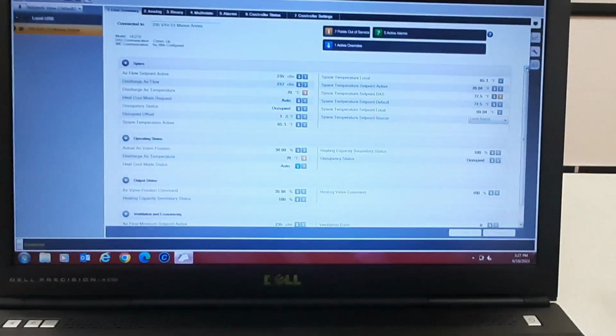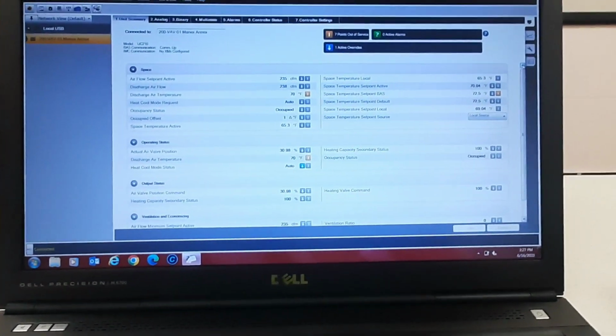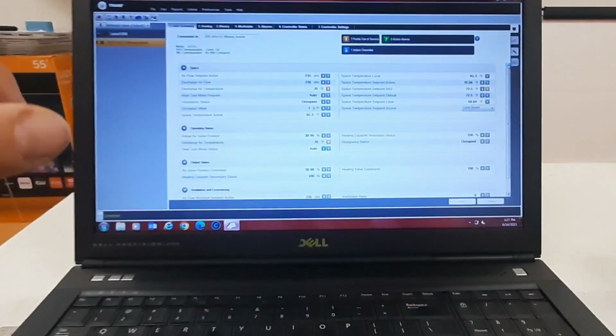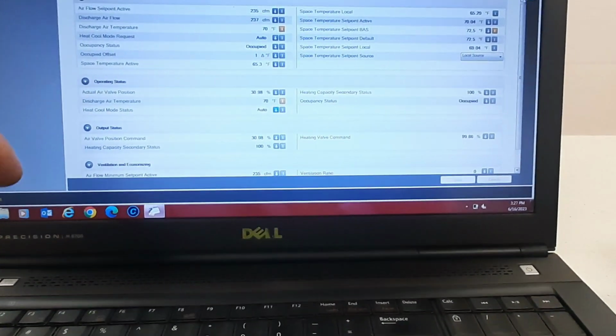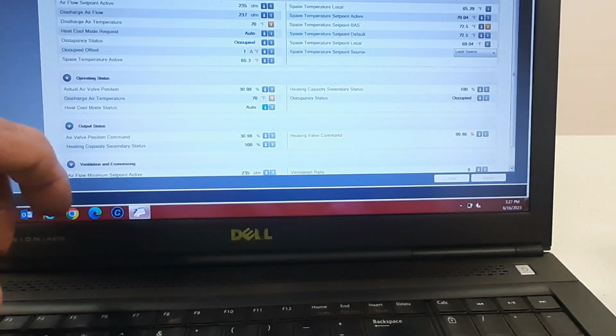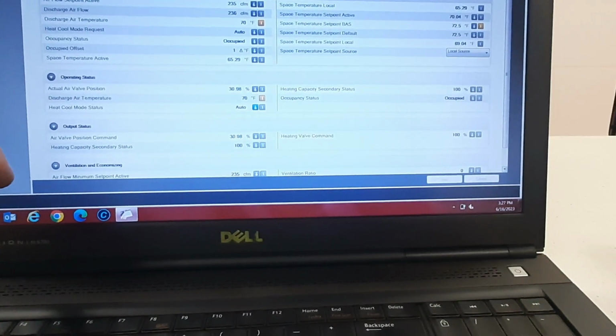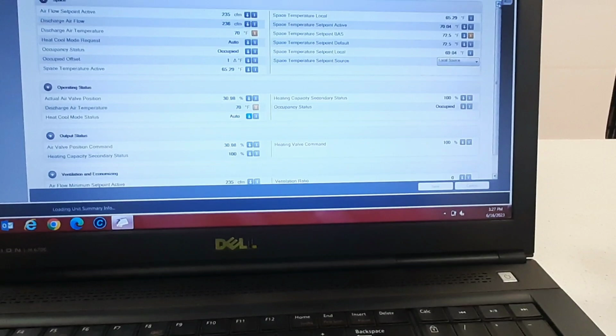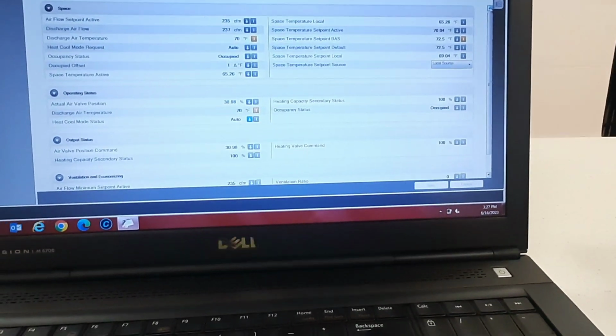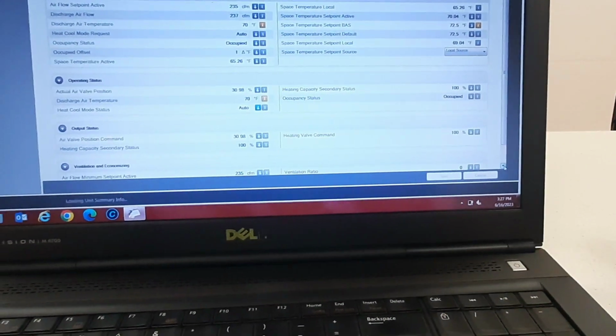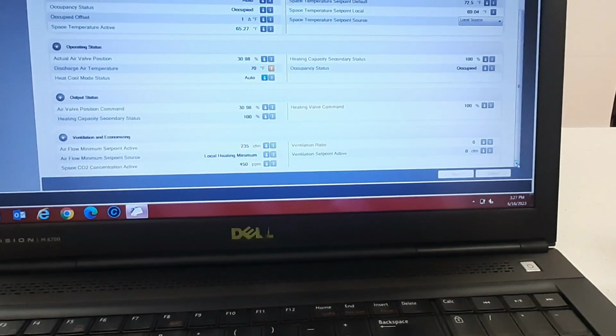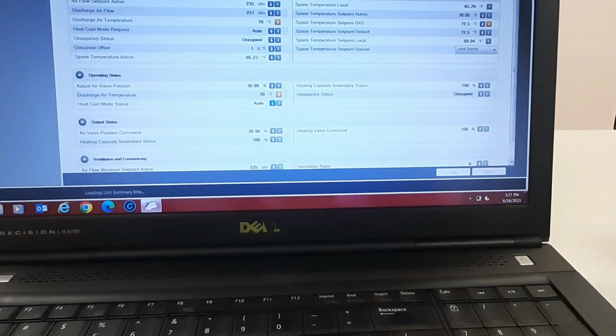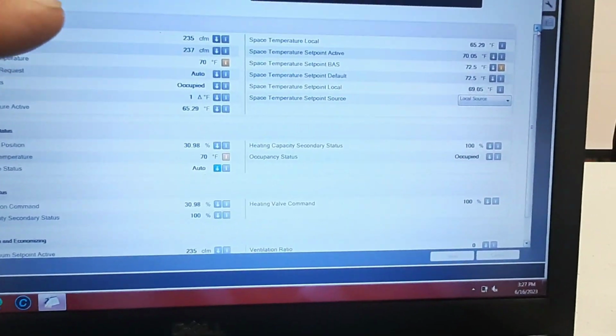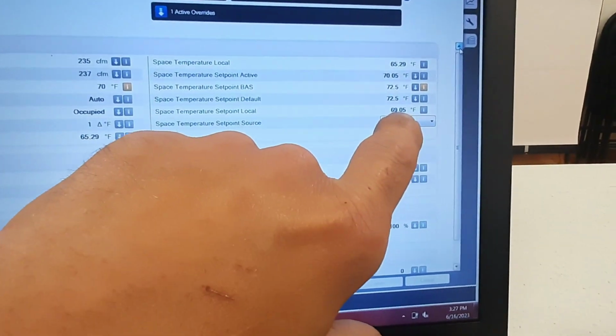So this thing, apparently where it was showing test, I don't know if it got stuck in that calibration mode or what. I was searching and looking through everything, and it finally kicked out of whatever, I'm guessing that calibration mode that I was in, or tried to be in, which I canceled out of because it wouldn't do anything. But it finally went to local heating minimum, which I have no local heat right now, so it's gonna freeze this place out. But we're doing 235 CFM. This is on, let's see, local set point 69. So it is truly operating off of the thermostat now.